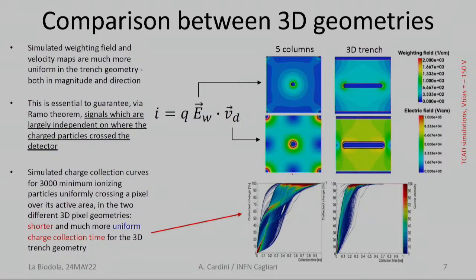The problem with this, well, you can see it here, practically. This is from simulation, but what is the reason? Well, the reason is the fact that the charge deposits which are far away from the central column will take longer to be recovered. So the shape will change as a function of the radius from the central column. So you need a parallel plate detector to achieve a uniform response all around your active area.